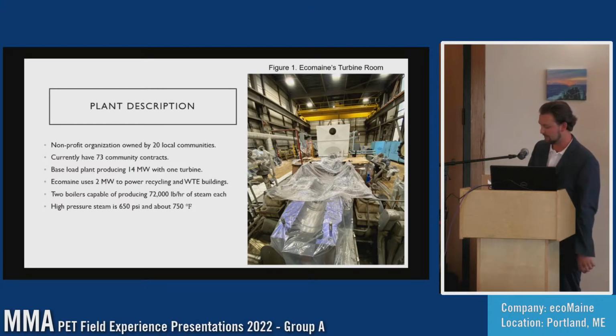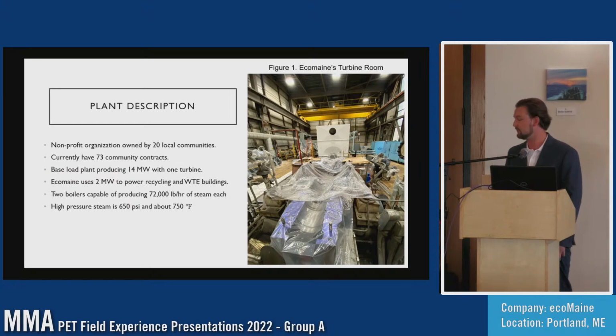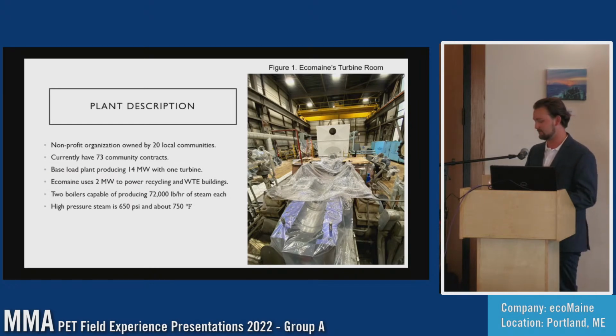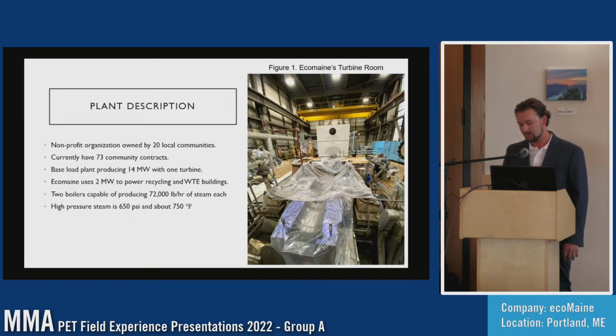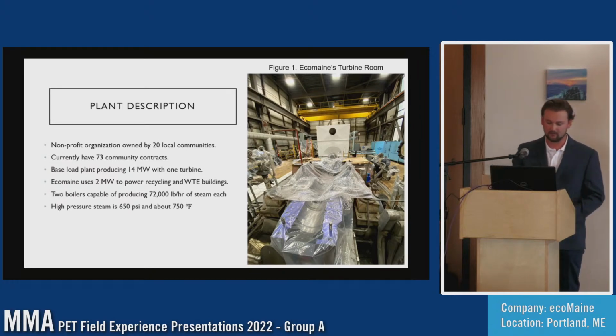Eco Maine has one turbine for both their boilers. Eco Maine uses roughly 2 megawatts of electricity to power their recycling building and their waste to energy facility. As previously mentioned, Eco Maine has two boilers capable of producing 72,000 pounds of steam an hour. The boilers produce steam at 650 psi and about 750 degrees Fahrenheit.